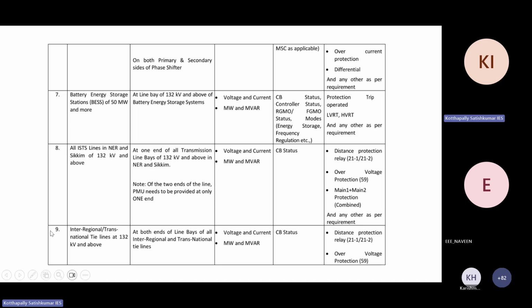As I told, it's inter-regional and transnational tie lines of 132 kV and above. You may get some ambiguity, since initially I said 400 kV, but now I'm saying 132 kV. It is very simple: for 400 kV and above, you'll place PMU at one end of the line, in general. But if it is an inter-regional or transnational line, for example a line between India and Nepal, or India and Bhutan, then even for 132 kV, you will place a PMU, because these are critical lines where we want to observe that data. Accordingly, we mandated them to place PMUs at these.